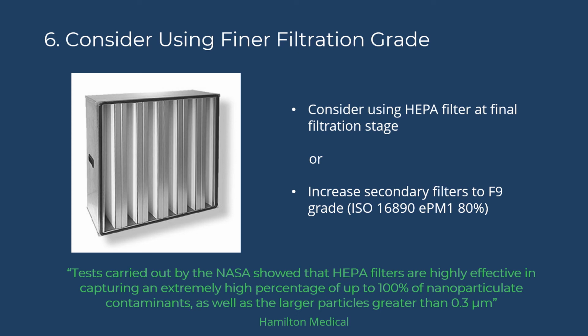A lot has been said over the last 3 months or so about HEPA filters. High efficiency particulate air filters are able to trap 99.97% of airborne particles of 0.3 microns in diameter or larger. For this reason, they are used as a final stage of filtration in buildings that require a higher level of contamination control, such as in hospitals, research laboratories, and certain food production facilities.